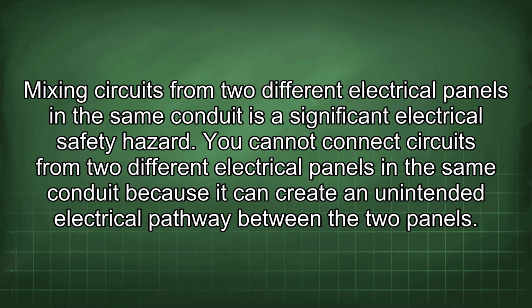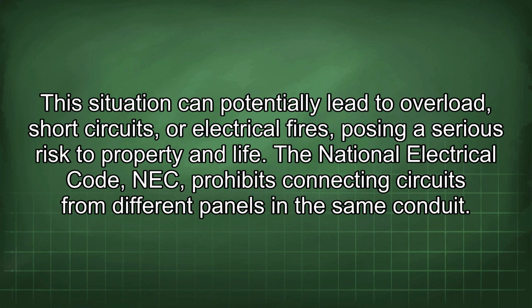Mixing circuits from two different electrical panels in the same conduit is a significant electrical safety hazard. You cannot connect circuits from two different electrical panels in the same conduit because it can create an unintended electrical pathway between the two panels. This situation can potentially lead to overload, short circuits, or electrical fires, posing a serious risk to property and life.